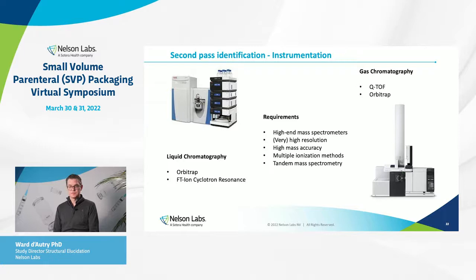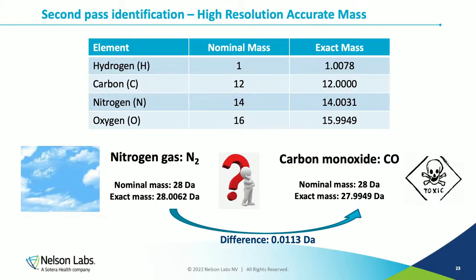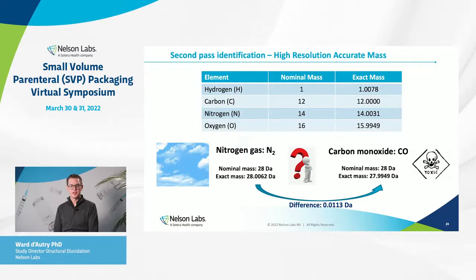For second-pass identification you need high-end mass spectrometers with very high resolution and high mass accuracy, capable of tandem mass spectrometry. For gas chromatography, quadrupole time-of-flight or orbitrap systems are used; for liquid chromatography, orbitrap or ion-cyclotron resonance systems. To illustrate high resolution: nitrogen gas N₂ and carbon monoxide CO both have a nominal mass of 28 daltons, but their exact masses differ by only 0.0113 daltons. At resolution 100 or 1,000 the two peaks overlap completely; only at resolution 10,000 can the two be distinguished — critical, since N₂ is harmless while CO is a lethal gas.